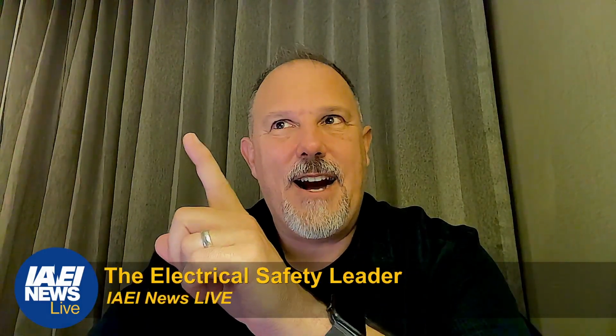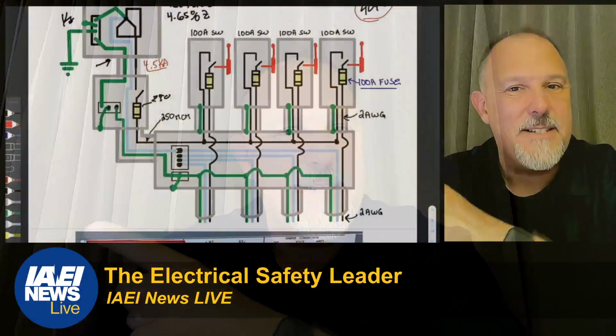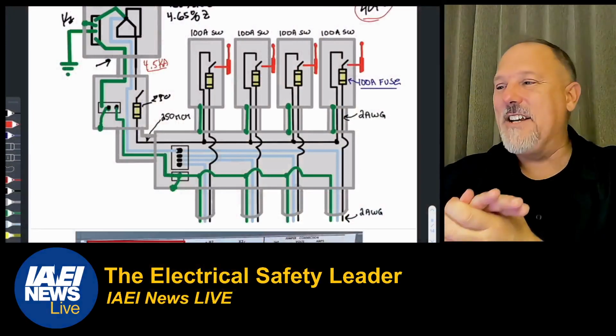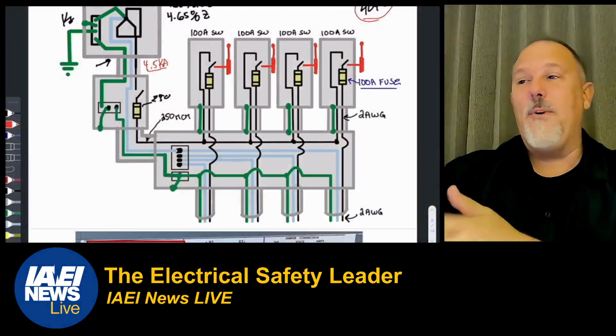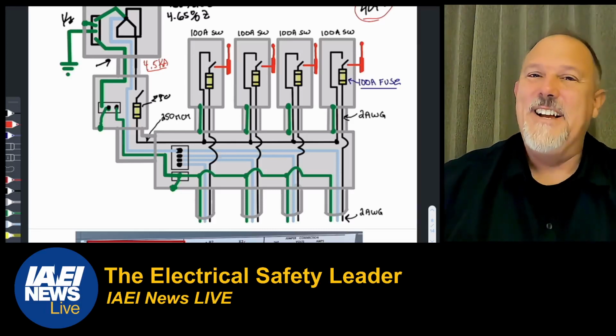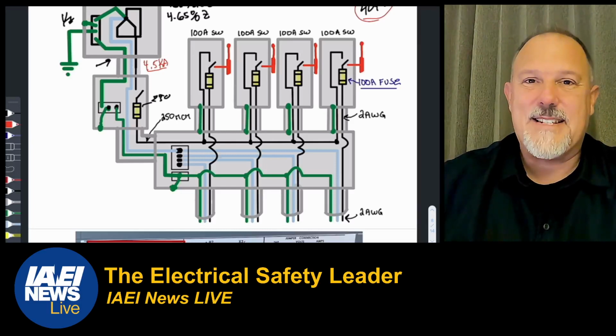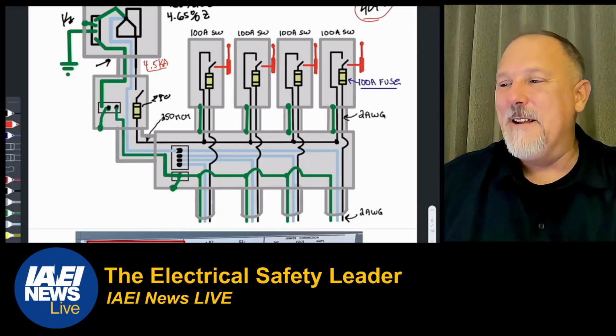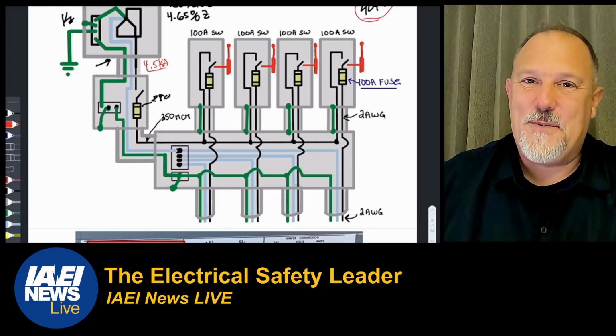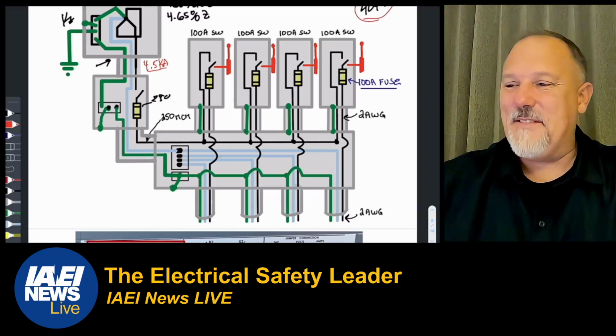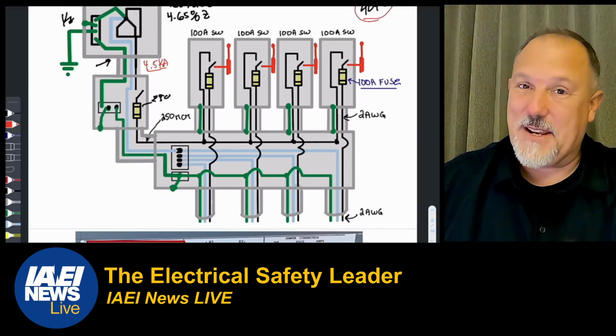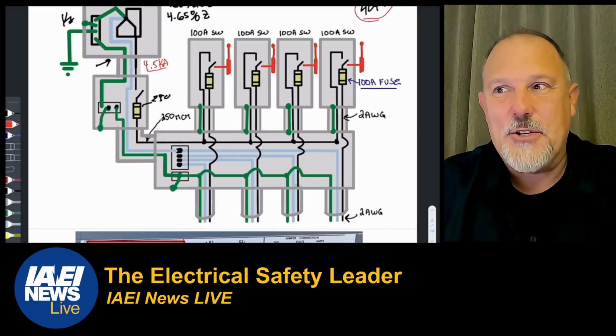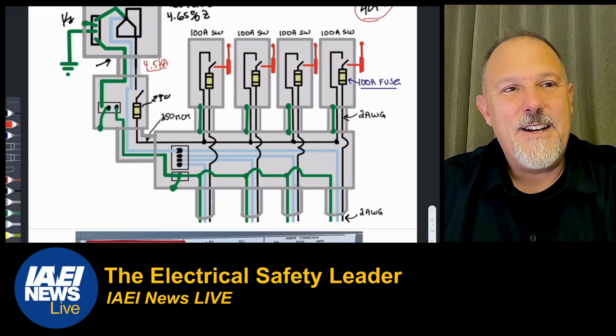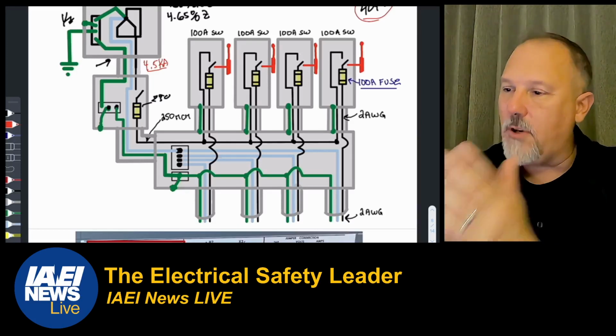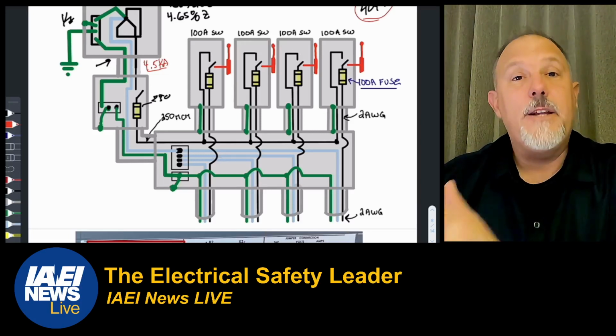And I have been going to these IAEI meetings, and when I look at a drawing like this, I can go, oh, that's Article 215, and well, this isn't Article 230 because that's not a service. It's Article 215 for feeders, and if that's outside, then it's 225 for outdoor feeders. And can't forget about Article 250 for grounding and bonding and sizing of that equipment grounding conductor. And you've got to think about Article 200. I could not do that before. It took a lot of time listening and walking through applications like this and trying to answer questions.